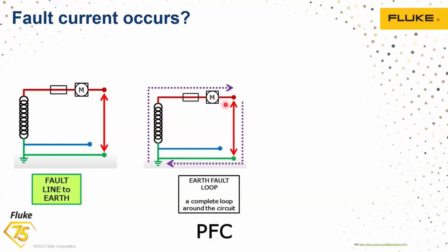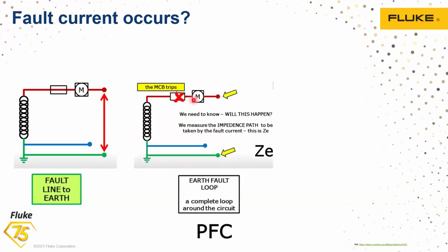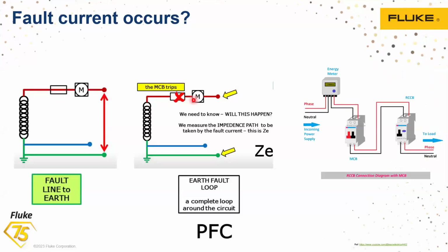main phase, and it can easily pass through the equipment. From this high current, what happens to the equipment? Over a period of time it gets damaged, or it may even create a fire. Some of the fuses are designed in such a way that they break immediately and stop the fault current from passing through. This is very important because the earth fault loop impedance measures the total loop impedance of the fault path, including the resistance of the conductors, connections, and the protective devices.